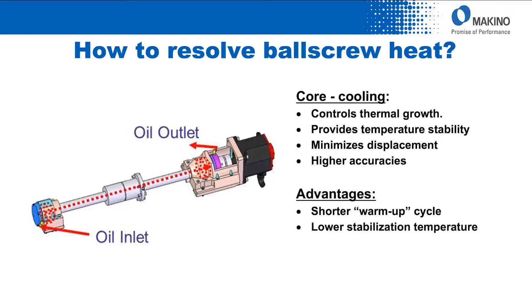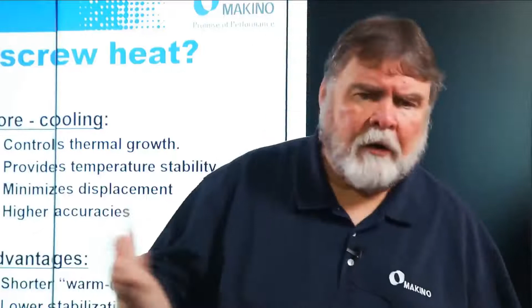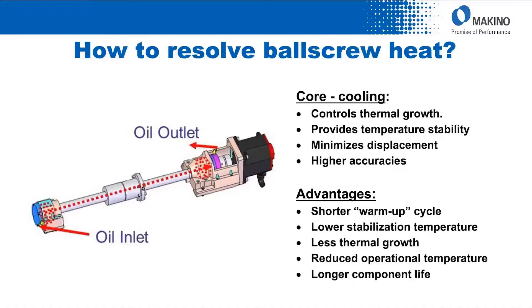What are the advantages? Well, number one, shorter warm-up cycles. Number two, lower stabilization temperature. What does it mean? Lower stabilization means less thermal growth, but it also means reduced operating temperatures. Anytime you can reduce the temperature of components, they're going to run longer, so longer component life.